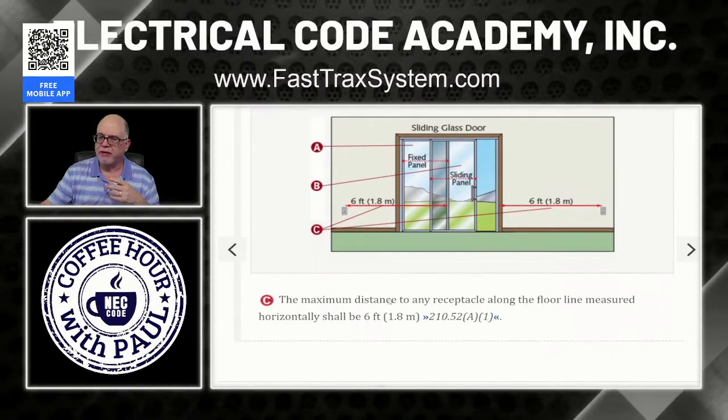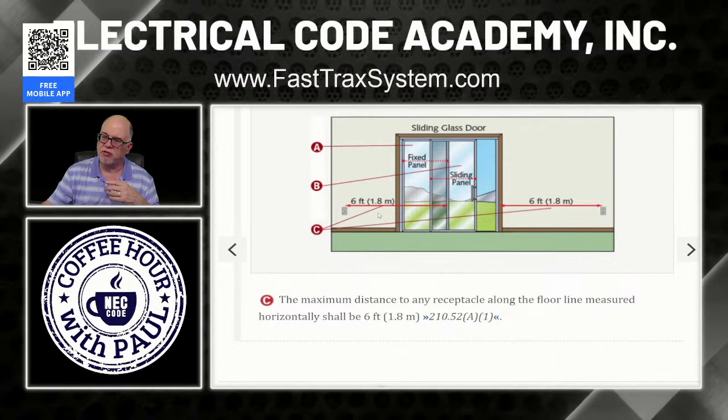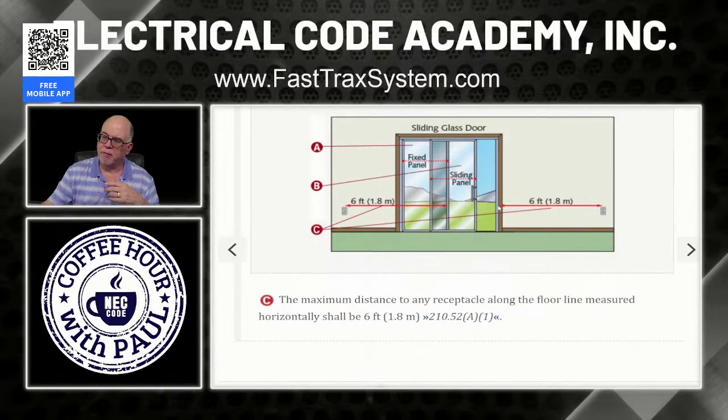Okay. So anyway, now let's look at C. It says the maximum distance to any receptacle along the floor line measured horizontally shall be 6 feet. Okay, that's in 210.52(A)(1). And so as you see right here, 6 feet from the break in the wall line, right there, that floor line at the wall, 6 feet. Right here, other side of the break, in that floor line, right here, measured 6 feet, receptacle. Now, could it be at 5, 4, 3, 2? Absolutely. But the maximum is 6 feet, okay?